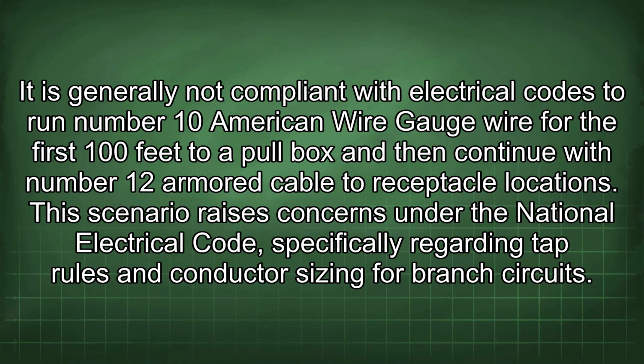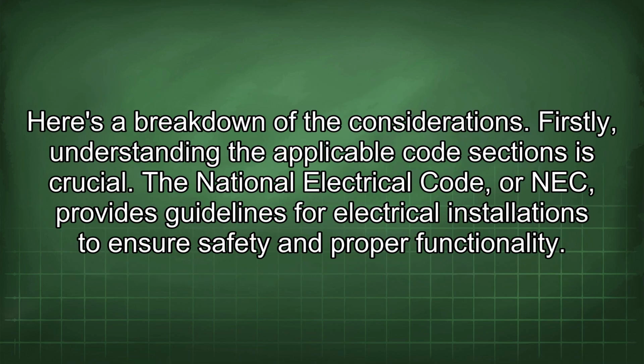It is generally not compliant with electrical codes to run number 10 American wire gauge wire for the first 100 feet to a pull box and then continue with number 12 armored cable to receptacle locations. This scenario raises concerns under the National Electrical Code, specifically regarding tap rules and conductor sizing for branch circuits. Here's a breakdown of the considerations.